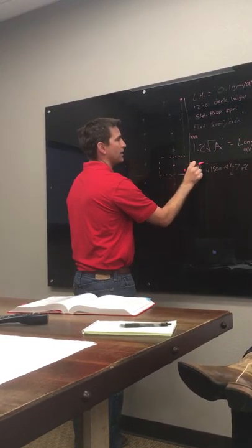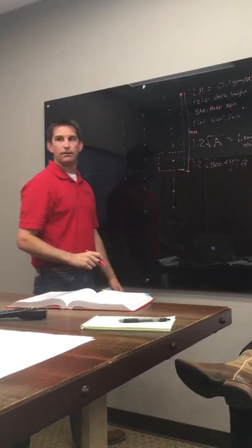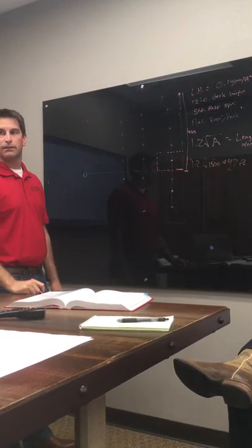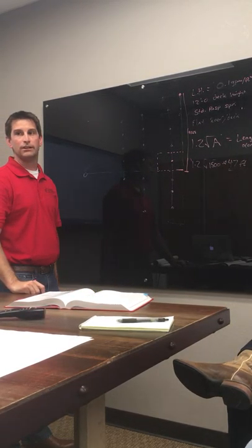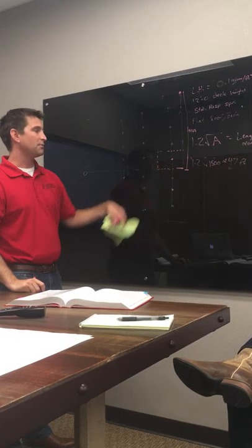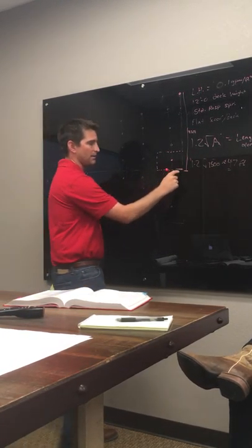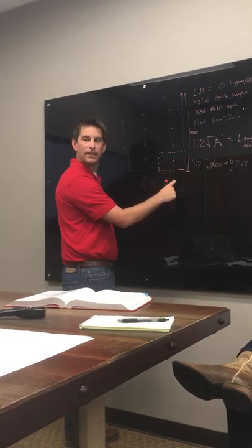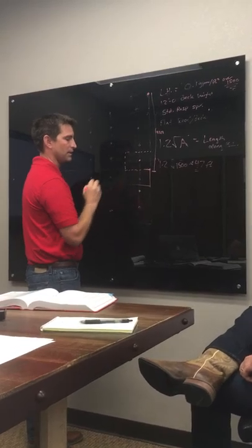So check this out. Let's say that I drew this and I said 47 feet actually was to right here. Then you're good? Yeah, I've got 47 feet of protection. Now that 47 feet is out of the protection of that head, so now you have to go to the end of that one. Yeah, because now I'm into this one. I actually have to pick up that whole extra head. So now I'd have to bring that remote area all the way down, include that, and then come across halfway.